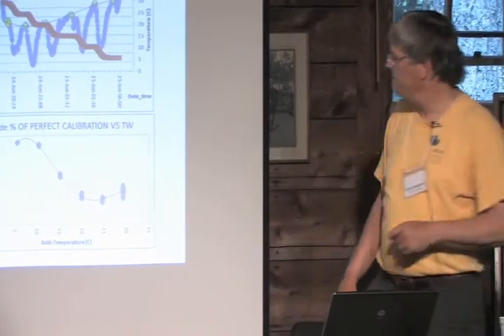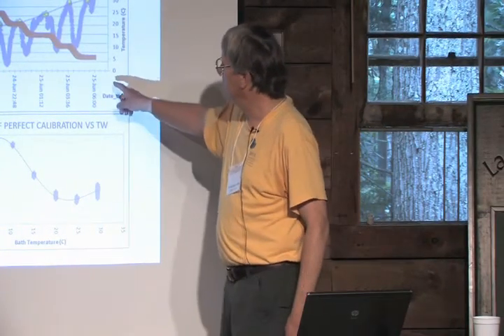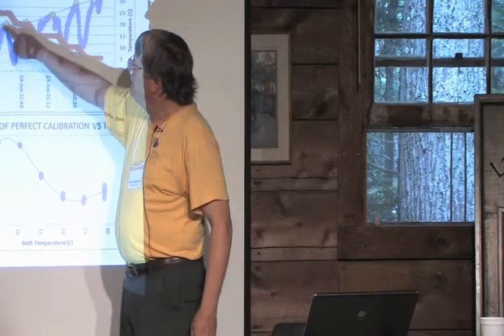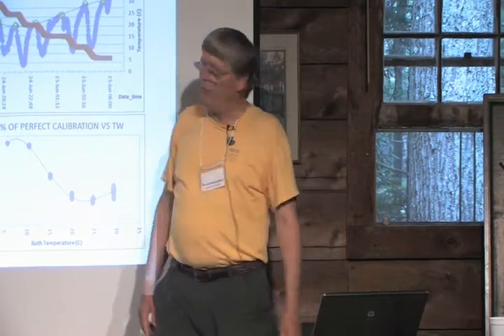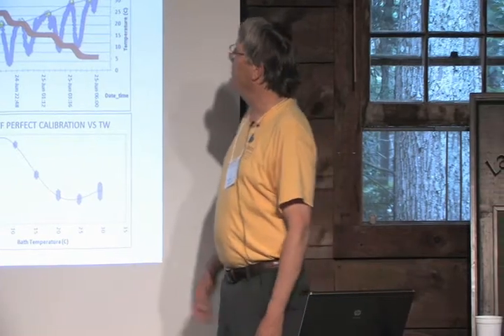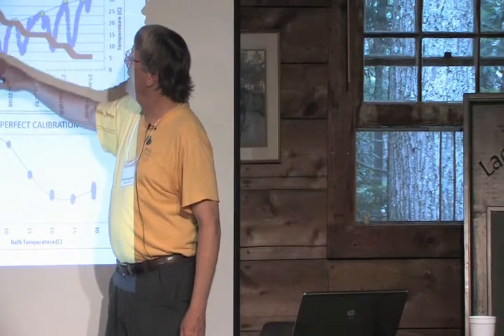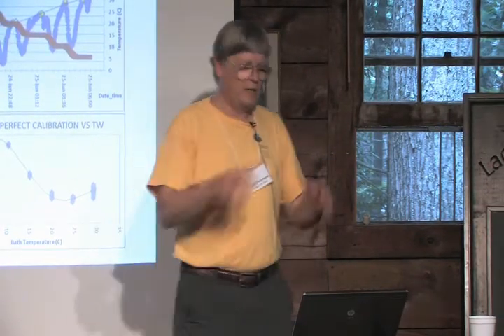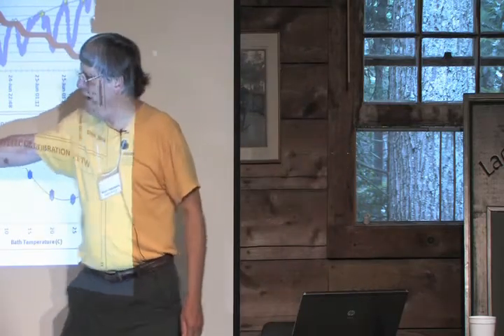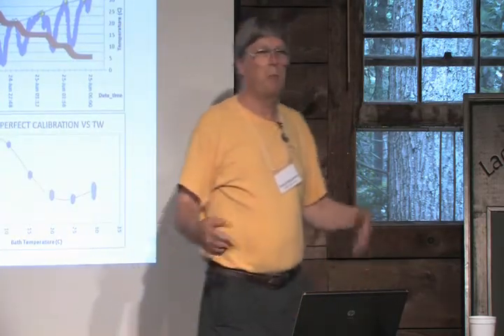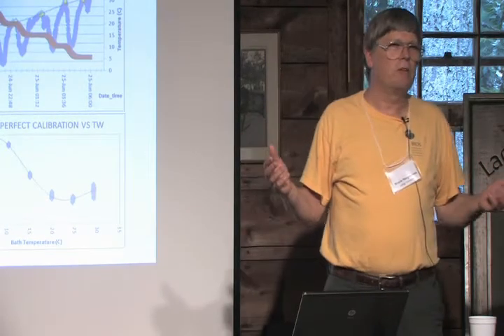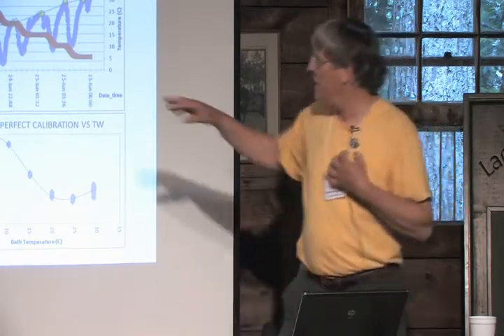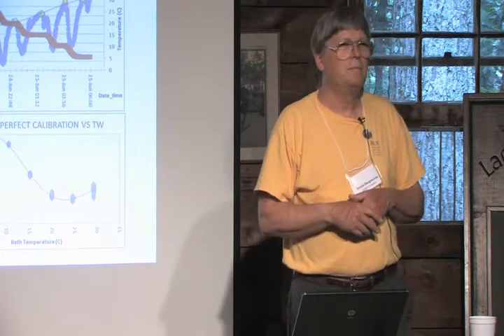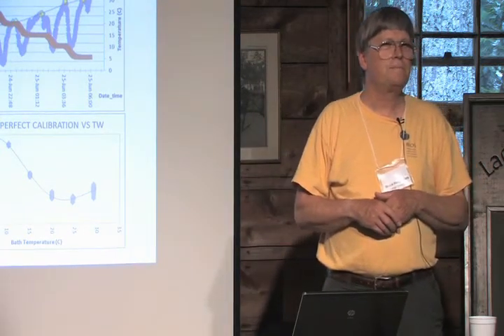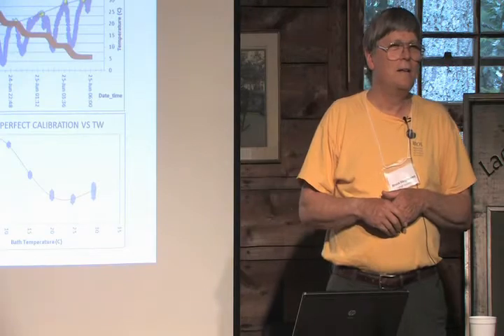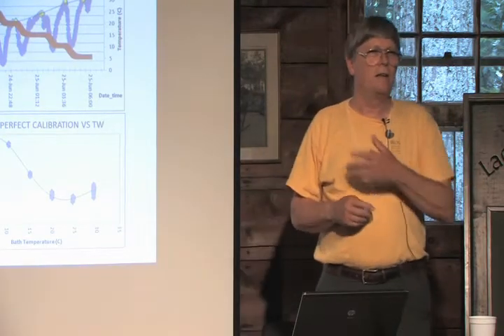Yes, sorry. What's the time frame on that return when you chill it? How long does that take? It takes about 45 minutes for the bath to change temperatures. And then it takes another 45 minutes or an hour. And this was in this 3.5 liter bucket with a couple of aquarium bubblers in there. So, you know, it took all day to do this test, and I would have rather done it longer. On the order of an hour. So if you set up a bubble water bath, you should probably wait an hour before thinking that it's stable. Yeah, and then look at the data.